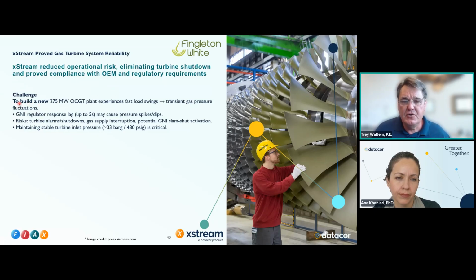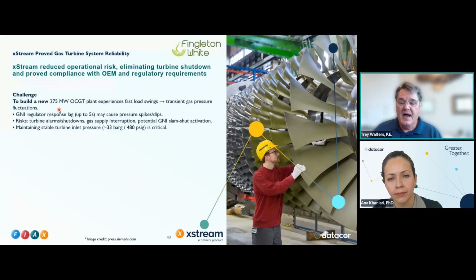The challenge was to build a new 275 megawatt open cycle gas turbine plant, but it can have fast load swings and transient gas pressure fluctuations. The gas regulator response could lag up to 5 seconds, which can cause pressure spikes and dips, turbine alarm shutdowns, gas supply interruption potential, and GNI slam-shut activation.